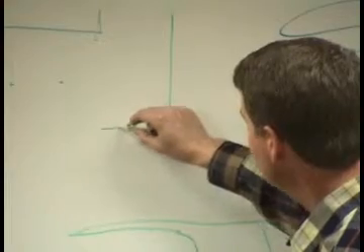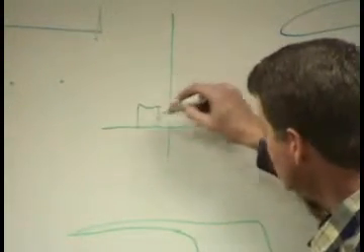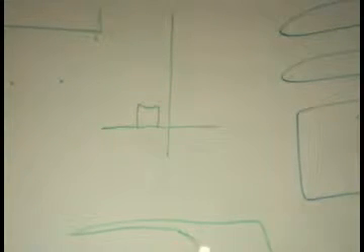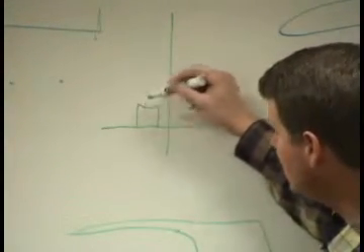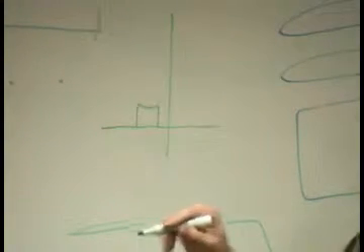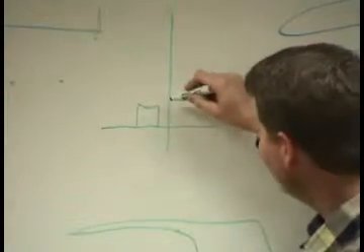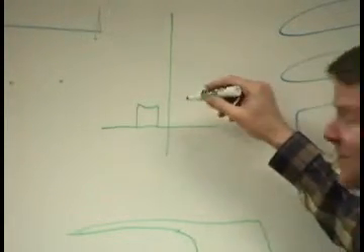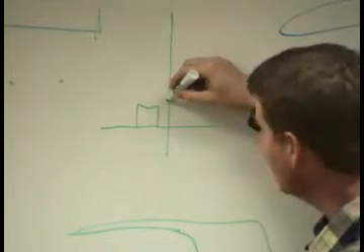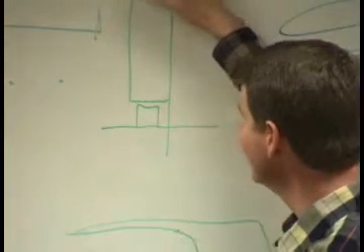I drive by a house that's not too far from my house, and here's the wall, and here's the ground level, and here's the air conditioner, which was too close to the house in the first place. You read the book and it'll tell you to put it like 24 inches away from the house. This is a nice top discharge. Well, they really wanted to save energy in this house, so they added a fireplace. But the air conditioner was there on the side of the house, so they framed out like this and put their fireplace flue coming off of there. And I ain't kidding you, that top of the air conditioner to the bottom of that chimney is like 6 inches. I can't believe that sucker works at all.